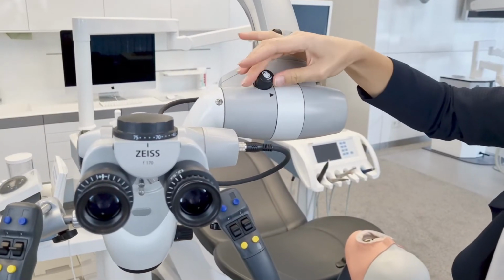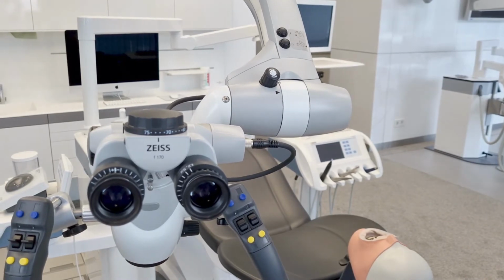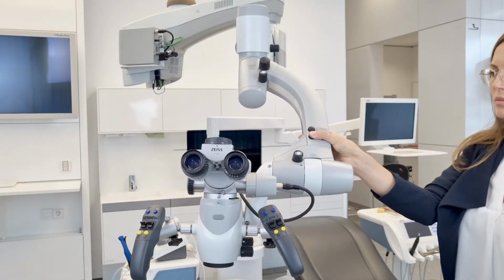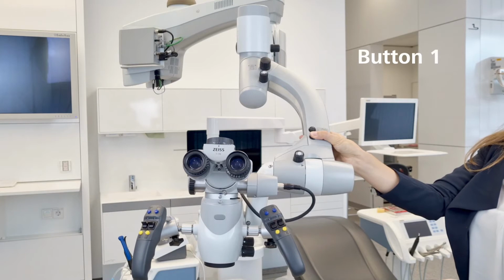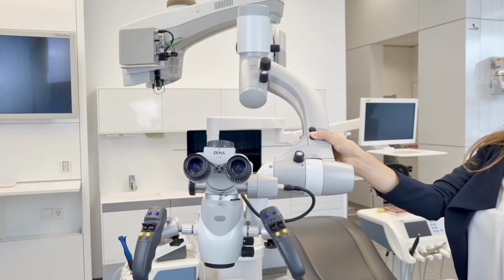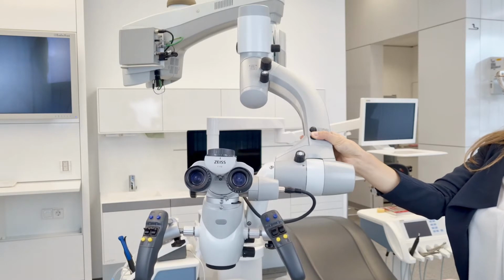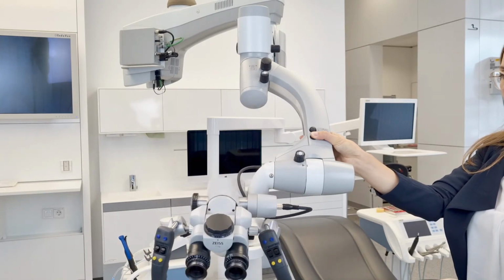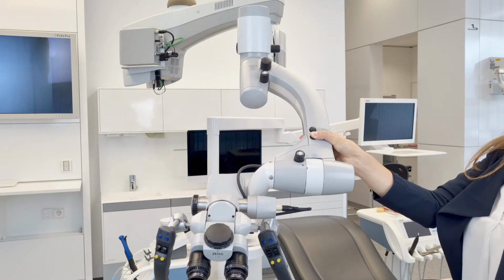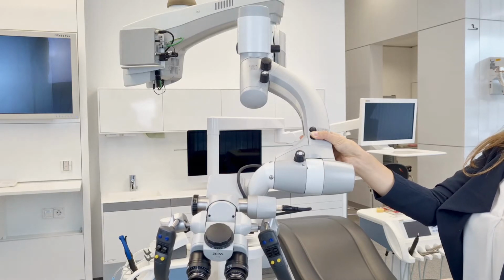Next, balance the tilt motion. Open the friction knob of the tilt motion. Press and hold button 1 until the motor of the balancing system stops. This decouples the surgical microscope from its suspension. This might take a few seconds. After decoupling, the surgical microscope has adopted its center of gravity position.